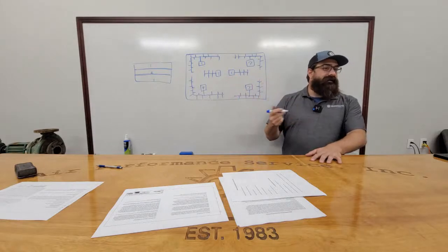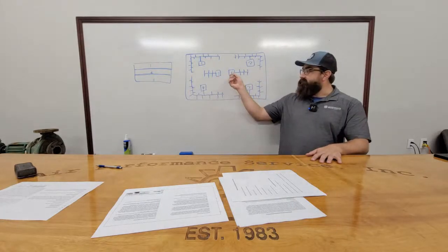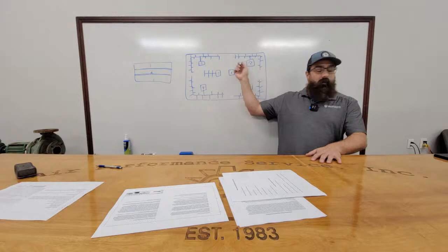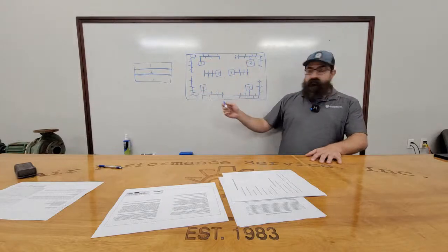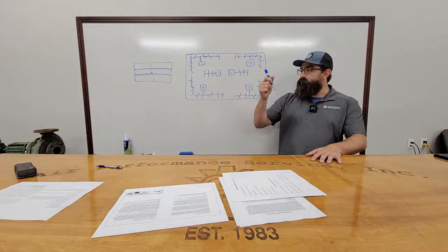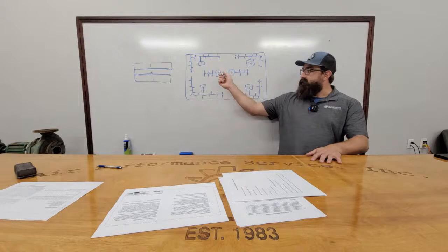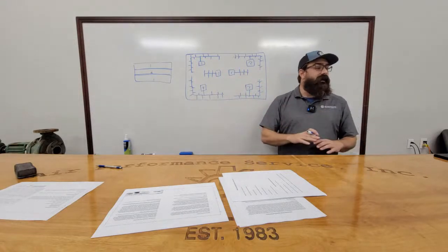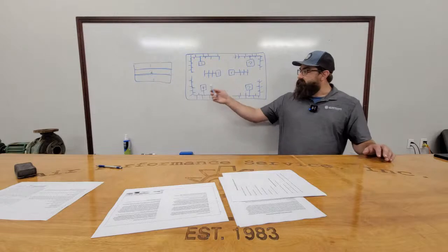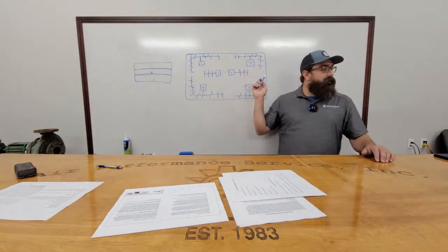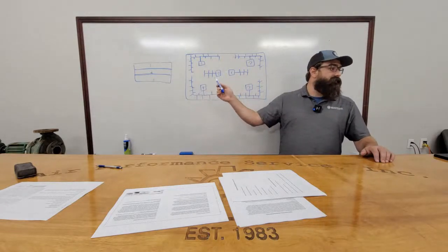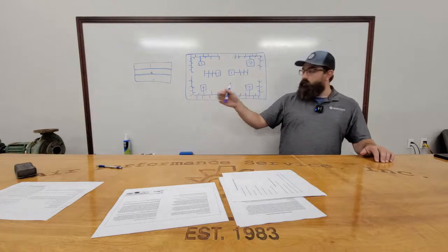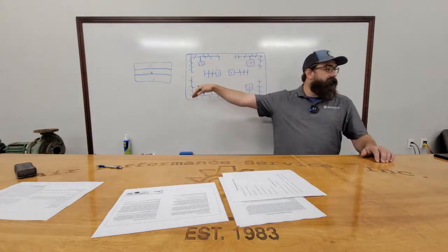At night, to save energy, they actually completely shut down their interior units and only run the exteriors. So their night program for unoccupancy is that any of their interior units are completely off. They don't care what the temperature is, because as long as they maintain the perimeter, the center will hold temperature. It doesn't rise or fall. It's all based on what is coming into the building.